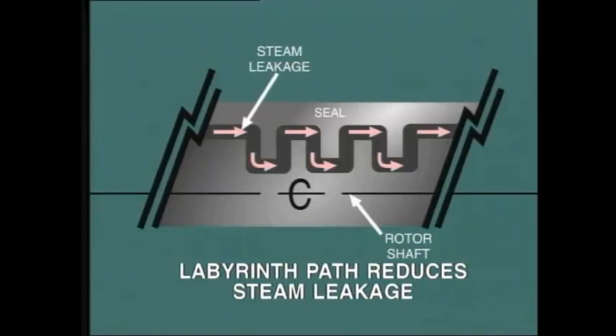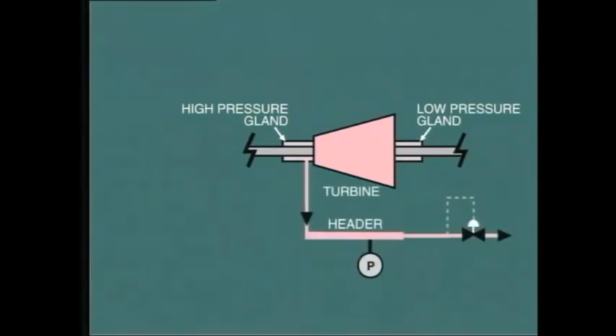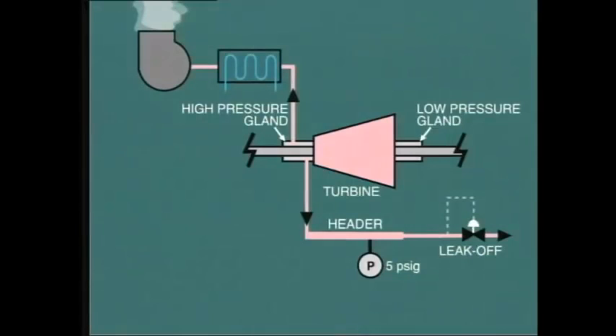Even so, there will still be some leakage of steam at the high pressure end through the gland seal. This leakage steam is extracted from the gland and fed into a low-pressure extraction point. The leak-off valve automatically adjusts the pressure within the gland steam header to maintain approximately 5 psig. But even at that low pressure, there will still be some leakage along the shaft into the turbine room. In order to prevent this steam from getting into the turbine room, it is drawn from the outside of the gland seal by a slight vacuum, which is produced by the gland steam exhauster. Some heat is recovered from this small amount of steam by passing it through a heat exchanger in the condensate system known as the gland steam condenser.